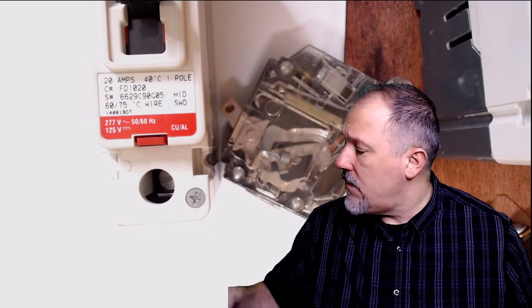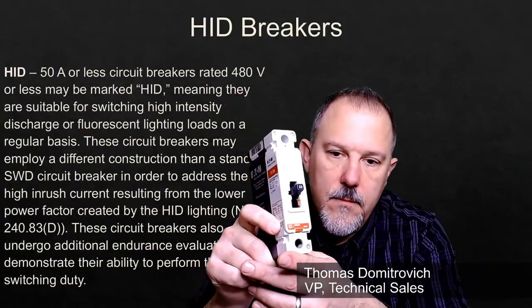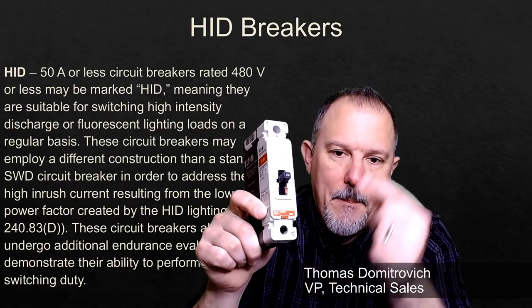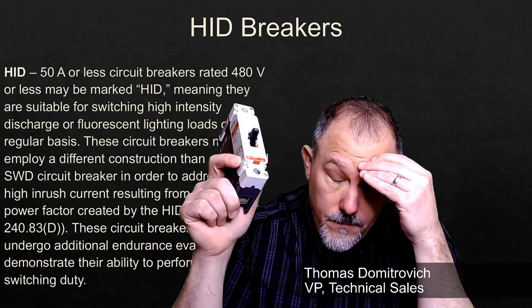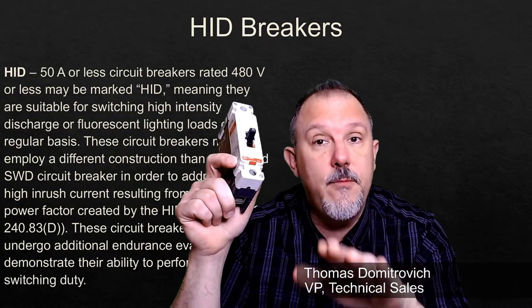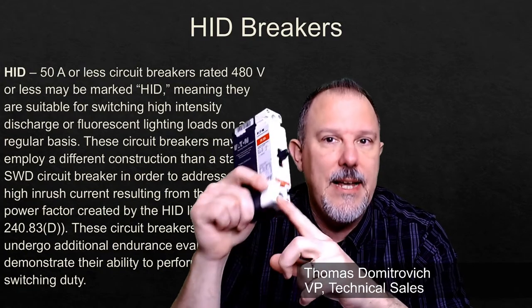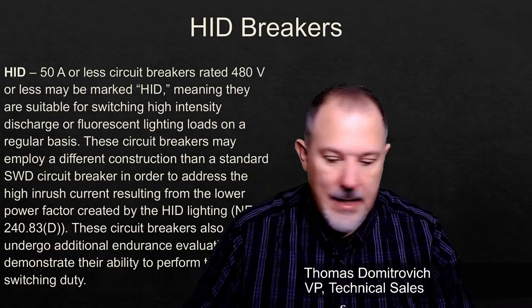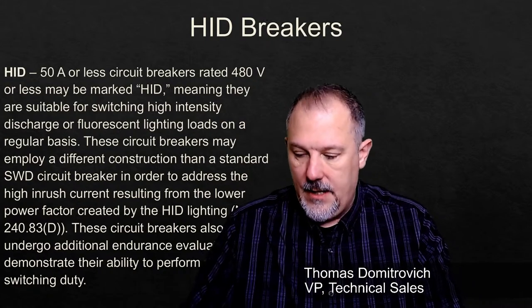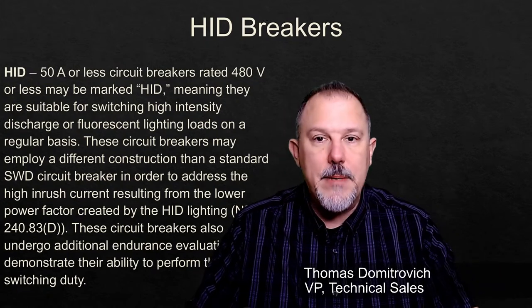Now, when I take this device and I land conductors, I go to my ampacity, I can use the 90 degree C column to do my calculations, but I can't exceed the 75 degree C ampacity because I need that amount of copper. Think about it. If I went to 310.16 in the code. Table 310.16.